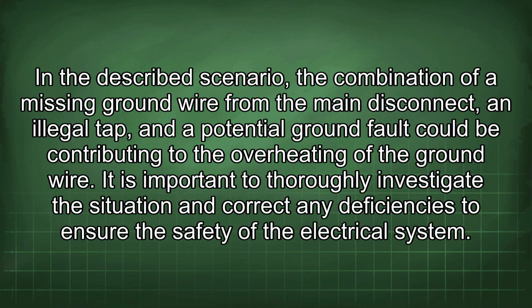In the described scenario, the combination of a missing ground wire from the main disconnect, an illegal tap, and a potential ground fault could be contributing to the overheating of the ground wire. It is important to thoroughly investigate the situation and correct any deficiencies to ensure the safety of the electrical system.